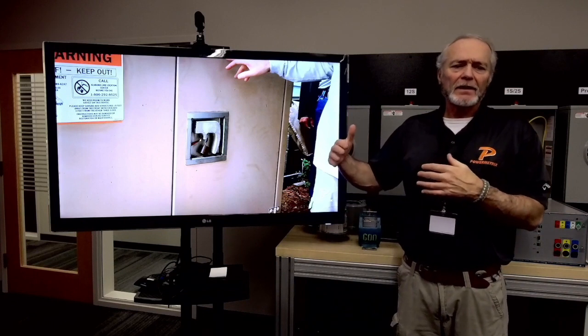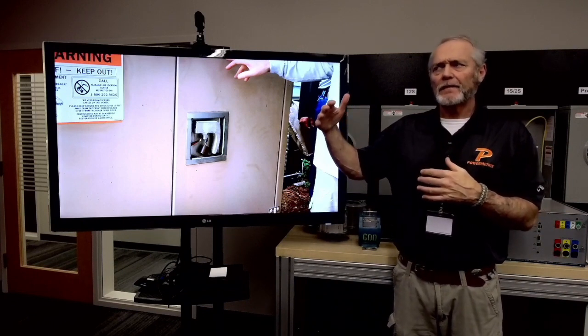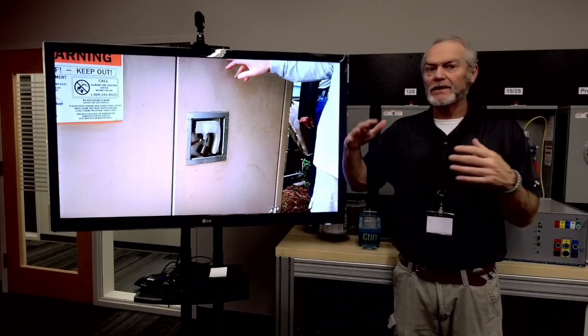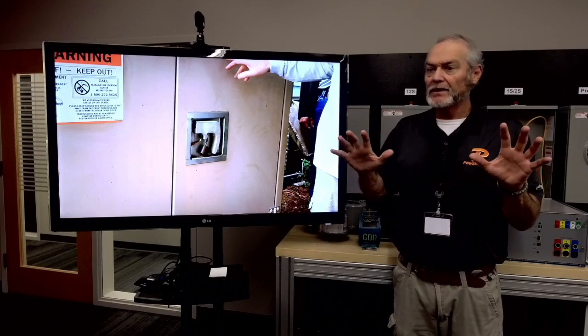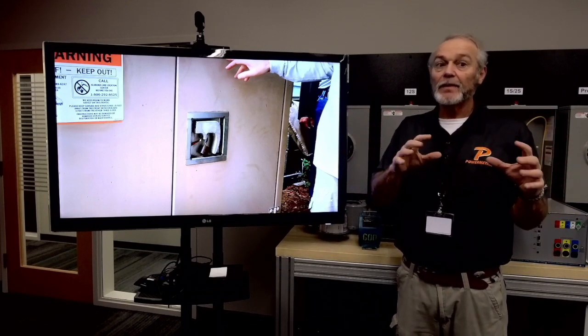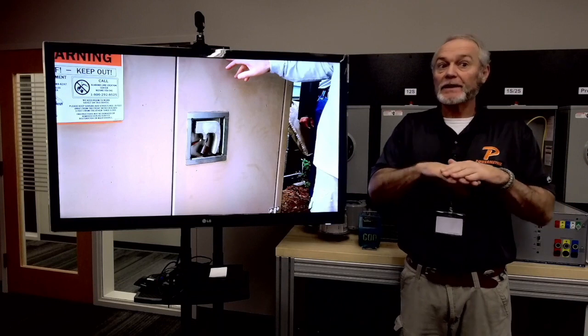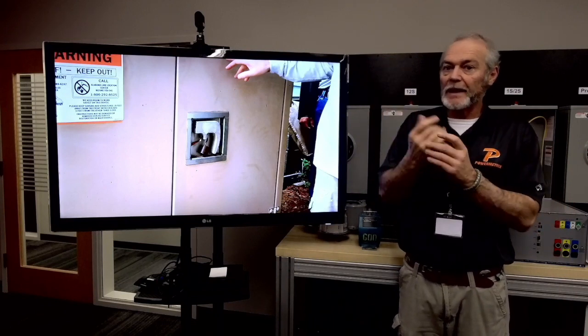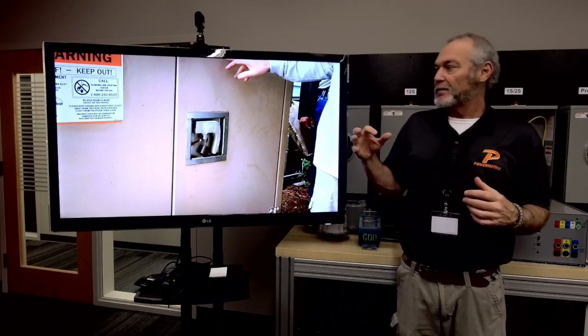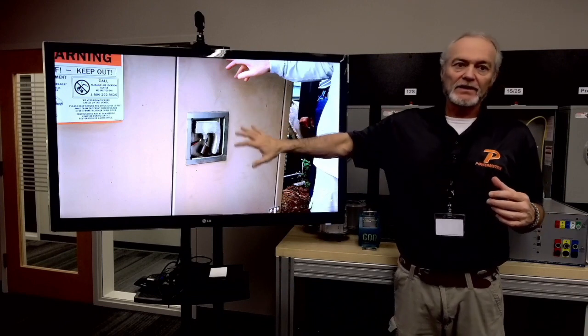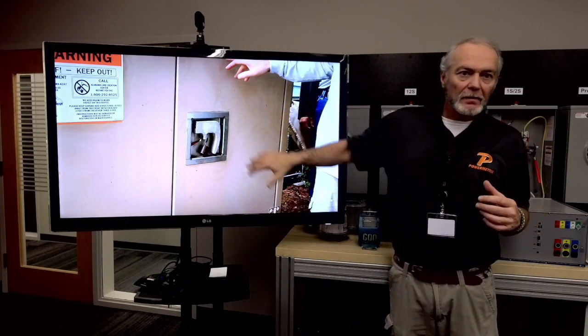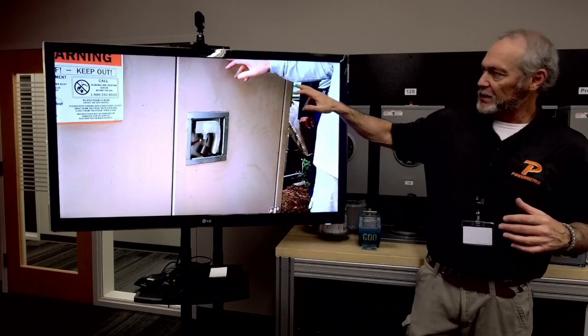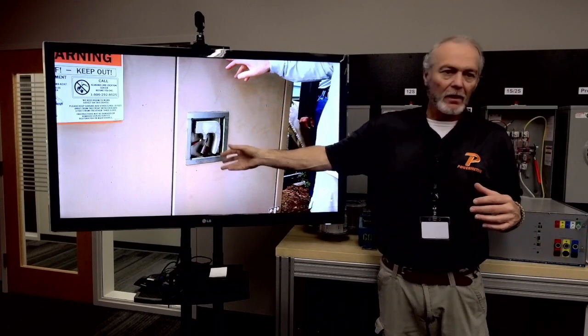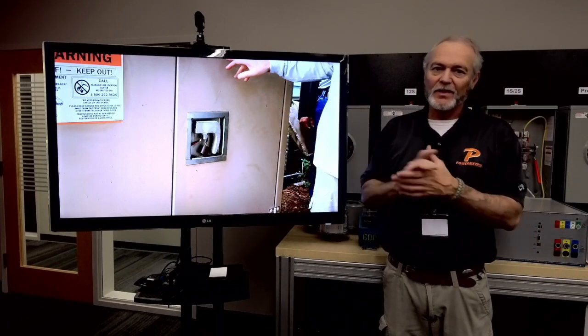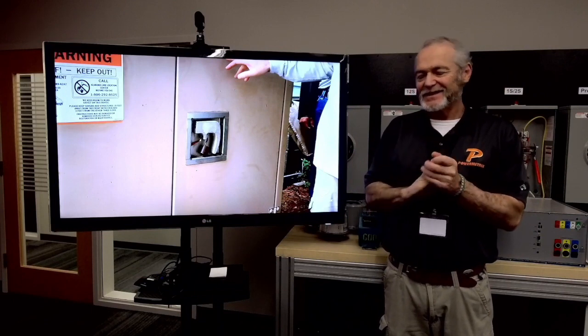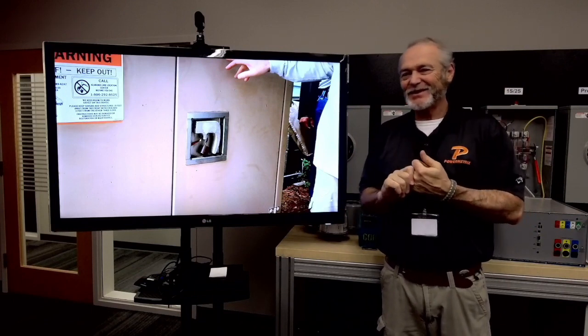We'll talk about it in a minute—the level of protection depends, and it's always different at your utility, so always defer to your utility's rules. But remember, those are minimums; you can always go safer or use higher rated gear. At minimum I should have had distribution level gloves on, my 1,000-volt gloves, before pointing and touching the transformer and holding that lock. Again, don't do as I do, do as I say.